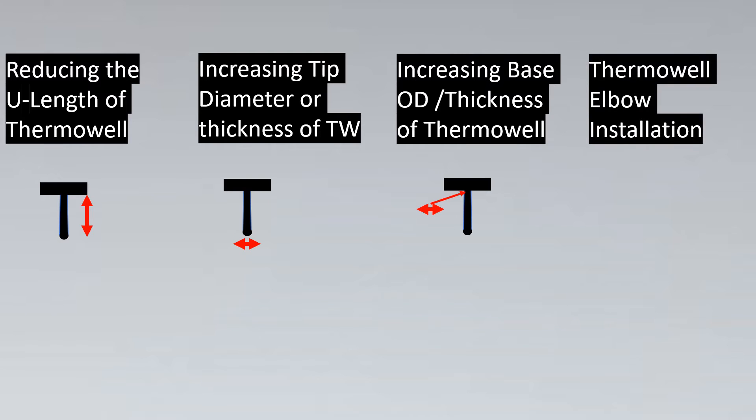If this is not feasible, then we can install the thermowell on an elbow. The elbow installation of thermowell is another option. As per ASME PTC 19.3, they don't say that then you don't have to do wake frequency calculations, but majority of the time because of such an installation, the velocity is greatly reduced.